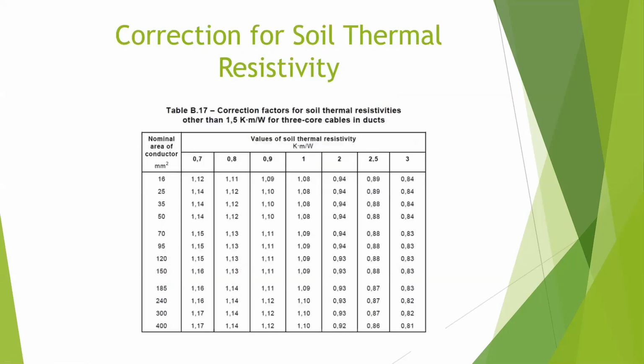And this is a very new one. I think you haven't used soil thermal resistivity in other designs. So usually the default soil thermal resistivity is 1.5 Kelvin meters per watt. And changing from that, we are going to have various rating factors depending on the conductor.